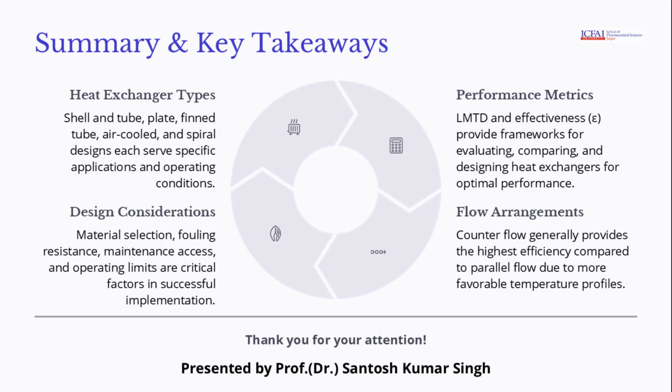In summary, heat exchangers come in various types, each serving specific applications and operating conditions. Key considerations in their design include material selection, fouling resistance, maintenance access, and operating limits. Performance metrics like LMTD and effectiveness are crucial for evaluating and comparing designs. Counterflow arrangements generally provide better efficiency compared to parallel flow, offering more favorable temperature profiles.